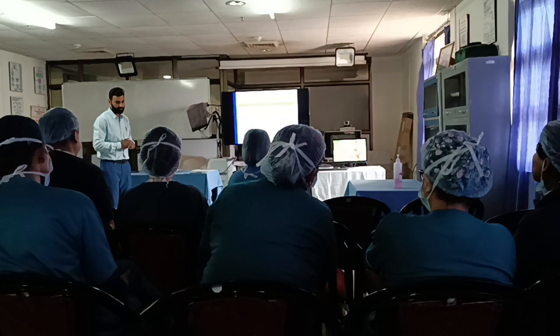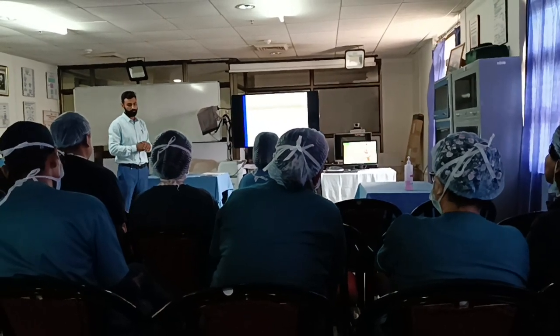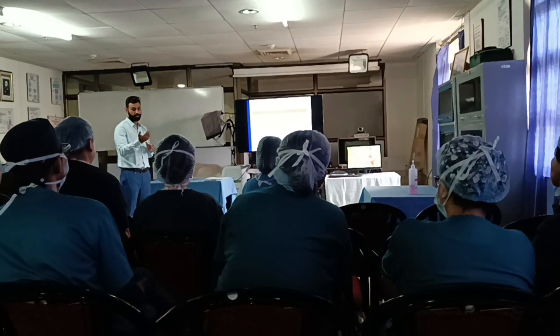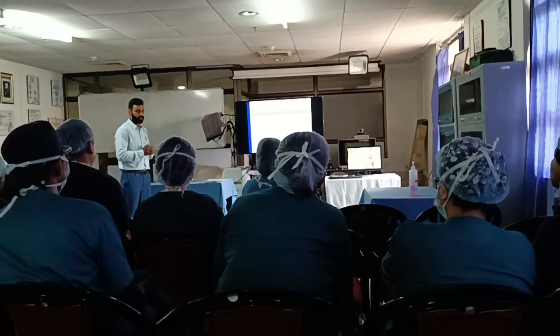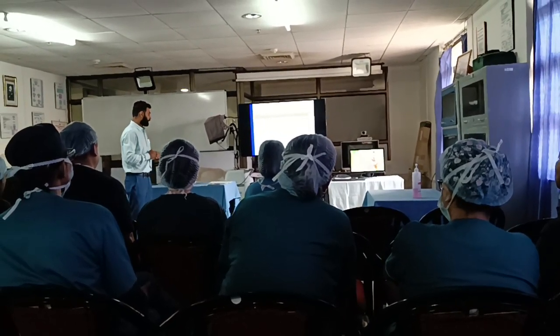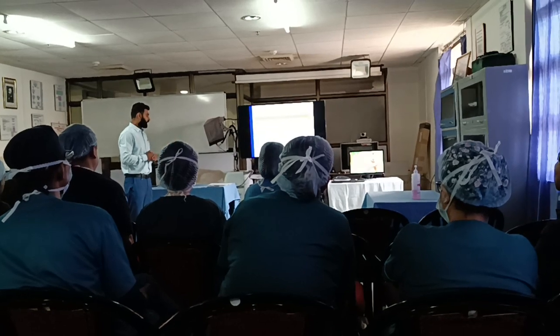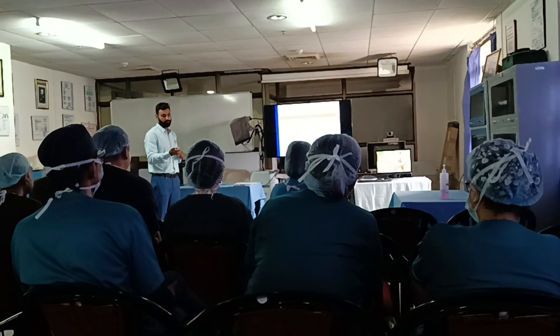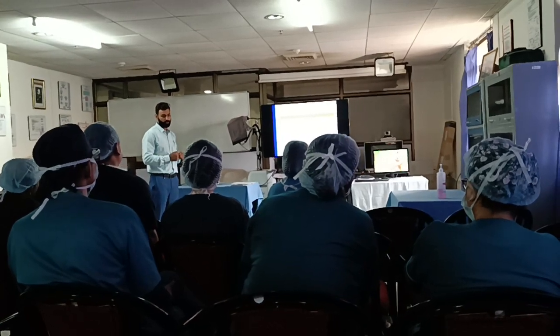Next is APTEM, where we use tranexamic acid to check for hyperfibrinolysis. So we can avoid unnecessary tranexamic acid when we are giving the baseline to the patient at the time of surgery. HEPTEM we include with INTEM because we are checking the heparin level, whether the reversal of heparin has been done or not.